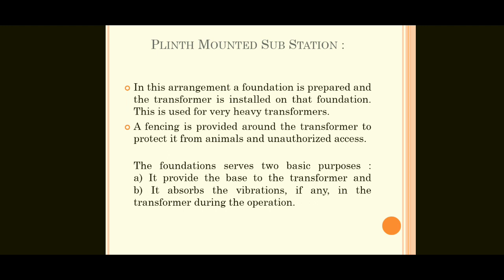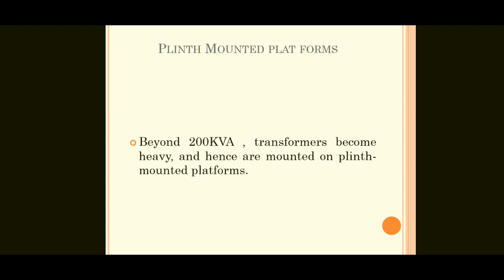So that is a major difference. Below 200 kVA use pole type, and above 200 kVA use plinth mounted transformers.